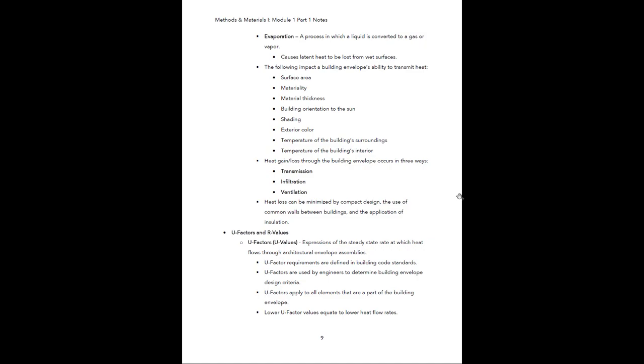We need to touch on U-factors and R-values. U-factors, also known as U-values, are expressions of the steady rate at which heat flows through architectural envelope assemblies. U-factor requirements are defined in building code standards. If you look at local building codes for building envelope assemblies, they'll have specifications about the U-factors a building needs to adhere to. U-factors are used by engineers to determine building envelope design criteria, and they apply to all elements of a building's envelope. A lower U-factor rating equates to a lower heat flow rate — the goal is to make it as low as possible.